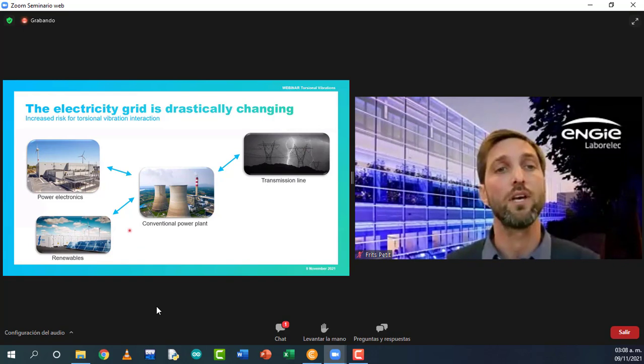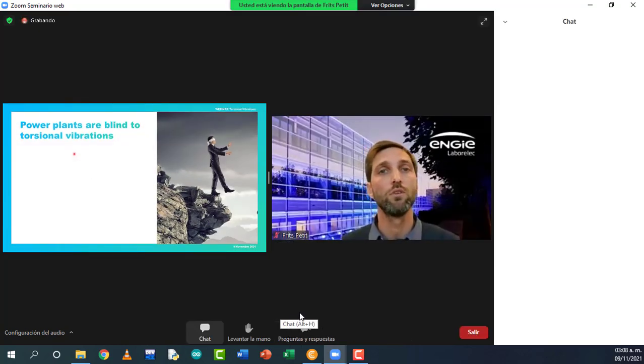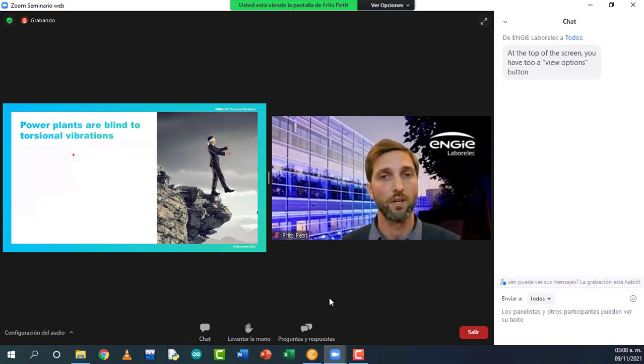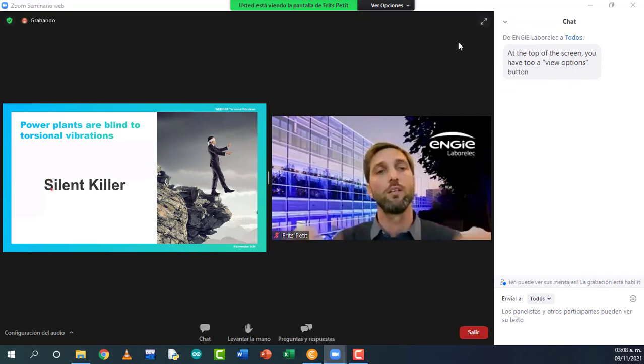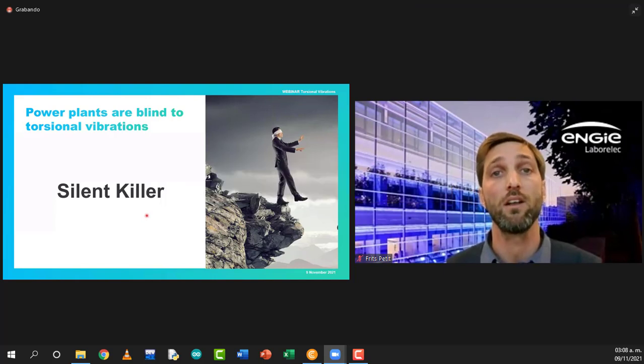And the key point here is that while you're connected with your power plant to the grid, this grid is drastically changing, but you do not see it at your power plant because in fact you are blind. The power plants typically do not have torsional vibrations as standard monitoring equipment. So this means that if something is happening, if an interaction is ongoing, exciting the torsional vibrations of your shaft line, you will not see it. Over time, the oscillating movement of the shaft line will accumulate fatigue damage. And so torsional vibrations are typically perceived as a silent killer. You do not see the damage happening, but when it happens and when the crack appears, it's too late.